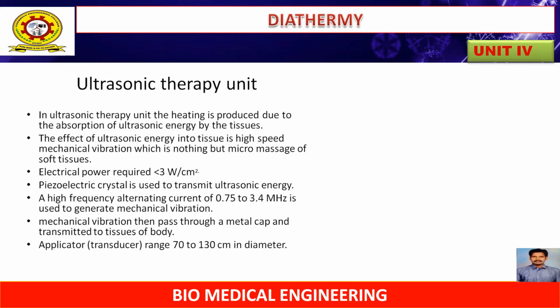The transducer through which the ultrasonic energy is applied to the patient uses a piezoelectric crystal. So for this operation, piezoelectric crystals are used for transmitting ultrasonic energy. High frequency AC current of 0.75 to 3.4 megahertz is applied to the crystal, where the vibration causes the mechanical vibration of the transducer, located directly in front of the crystal.